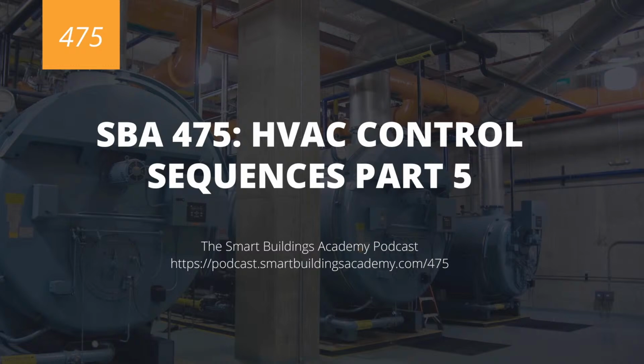And this is why you see steam utilized on a lot of large campuses, because you can pump so much energy into the same mass of media, or medium. So you've got the steam medium, and you're putting 970 BTUs into 1 pound versus putting 180 BTUs into 1 pound of water. So that's awesome. But it's also why it's so dangerous, because it transfers so much heat, and it's also why it's very hard to control. So steam is in 2 forms, right?